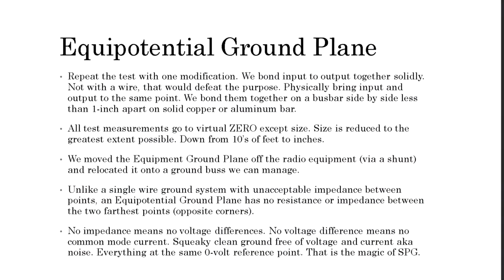Showtime. Okay, time for the magic of the equipotential ground plane. We're going to repeat the test, but we're going to modify the ground system a little bit. We're going to bond the input and output together solidly. We're not going to do it with a wire. That would defeat the purpose. Physically bring the input and output to the same point. We bond them together on a bus bar side by side, less than 1 inch apart on solid copper or an aluminum bus bar. We don't have to do the test to know what happens. All the measurements go to 0, except for the size.